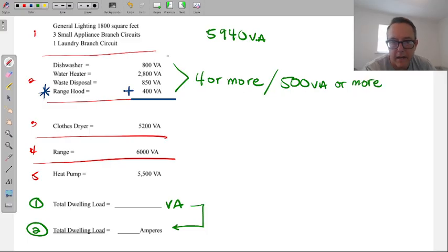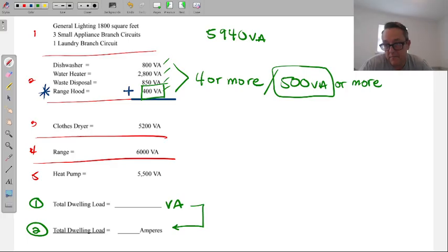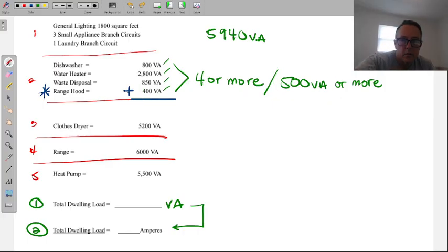So if we look at this, we have 1, 2, 3, 4, but if we look at the 4th one, it's not 500 VA. So now we can't use the 75% here. If that range hood would have been 500 VA or more, we would have been good, but it's less than 500 VA, so we can't use it. So therefore, no 75%, straightforward, add them all up, and that's that for this section.